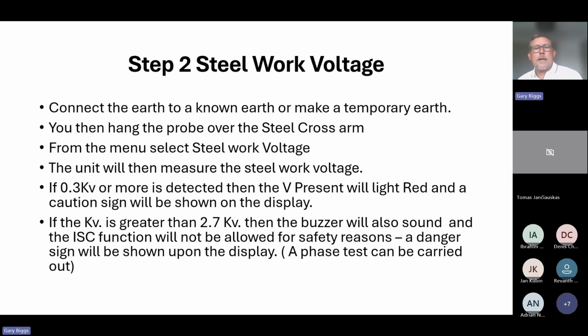If the voltage is greater than 2.7 kV, then a buzzer will also sound and the ISC function will not be allowed. Essentially, if you've got more than 2.7 kV there, you have got a significant problem. So there's no point measuring the potential milliamps because it's irrelevant.